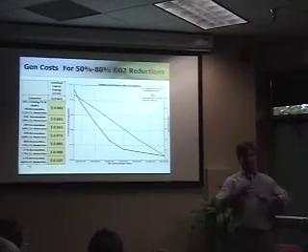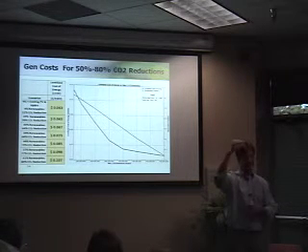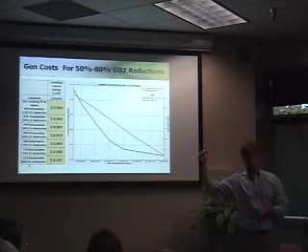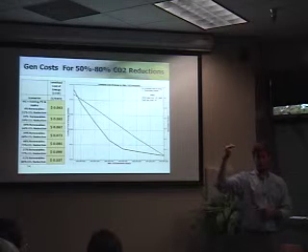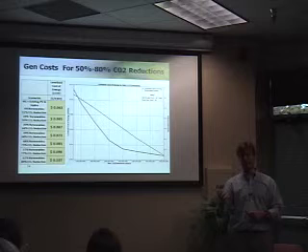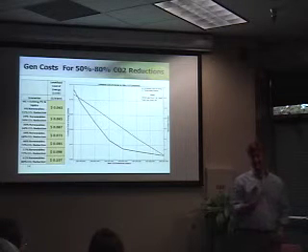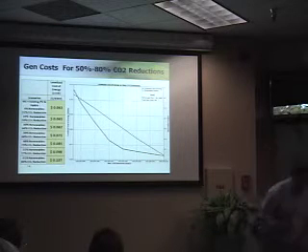You need all that natural gas capability for your reliability to start with. So buy it. It's cheap capital to buy that natural gas plant. Gas is expensive. Almost all the driver of gas costs are burning the gas. So as your renewables get cheaper, bring them on the grid, turn down your generators. Gas does not have the problem like coal does, that you can't turn it down and still maintain good efficiency.